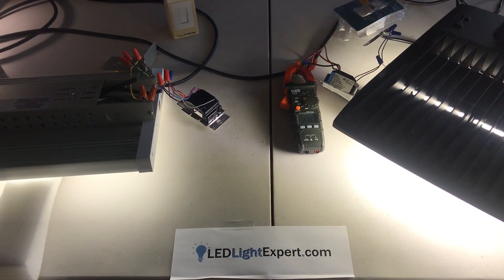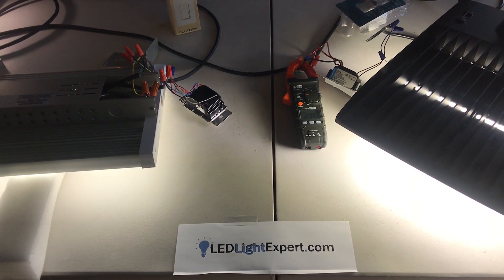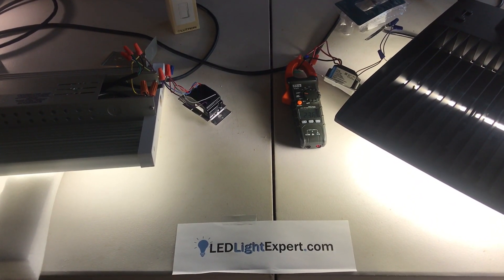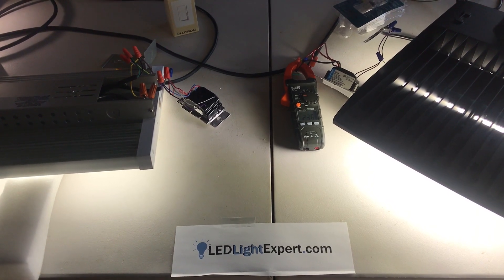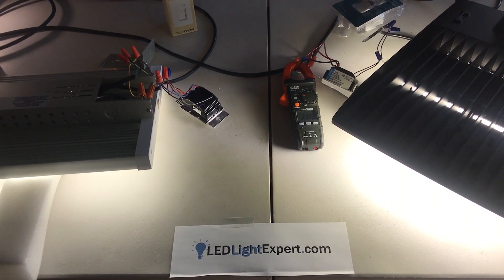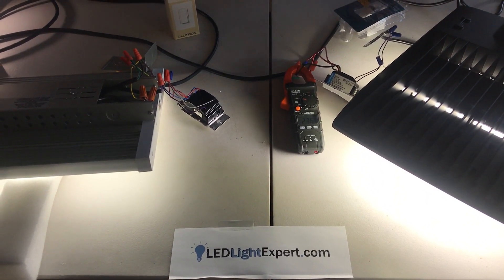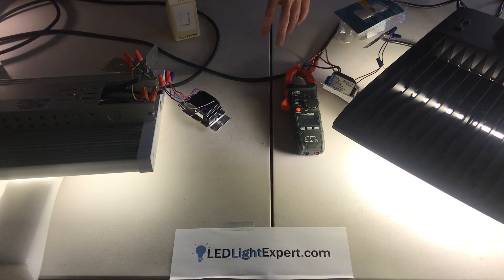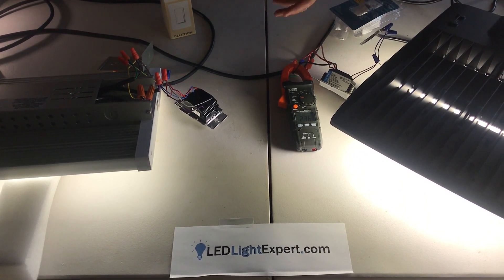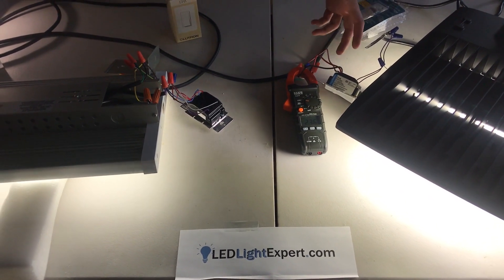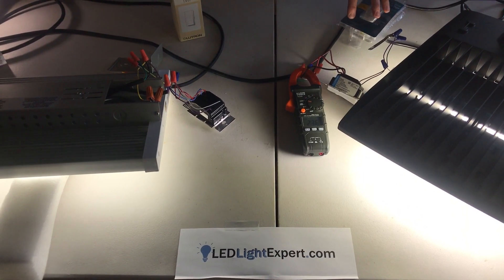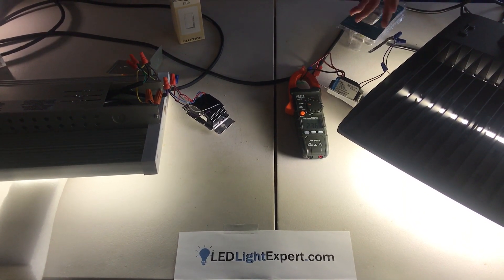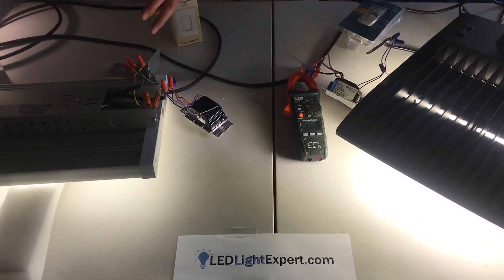Now last thing to keep in mind, possibly most importantly here, is that because this is a powered switch, it's going to have a watt or amp restriction on it. This one is not very high. It's only 450 watts. On a 300 watt parking lot light or 180 watt high bay light, you are going to go through that pretty quick.